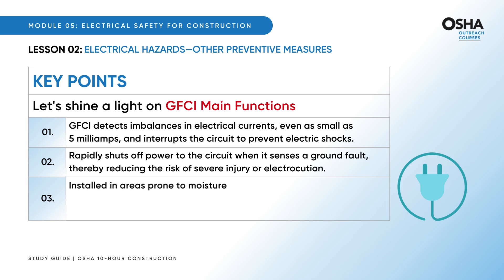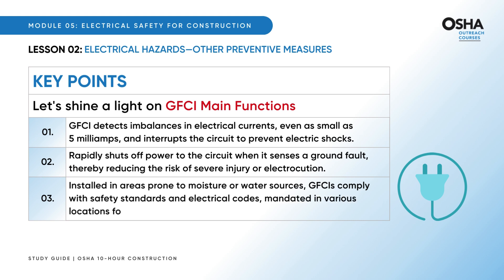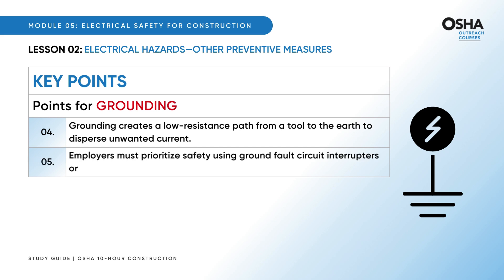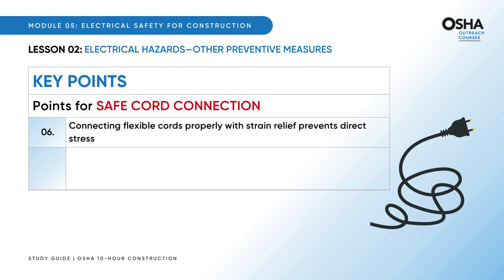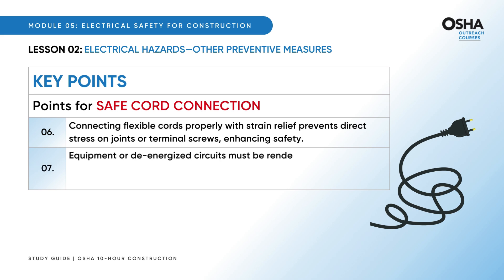GFCIs are installed in areas prone to moisture or water sources and comply with safety standards and electrical codes mandated in various locations. Grounding creates a low-resistance path from a tool to the earth to disperse unwanted current. Employers must prioritize safety using ground fault circuit interrupters or assured equipment grounding conductors at construction sites. Safe cord connection — connecting flexible cords properly with strain relief — prevents direct stress on joints or terminal screws. Equipment or de-energized circuits must be rendered inoperative and have tags attached at all points where they could be energized.